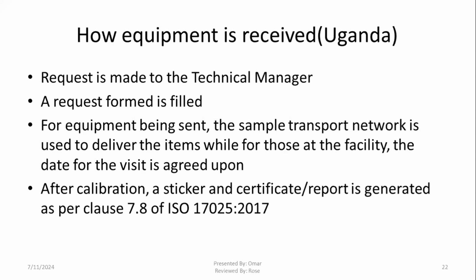So for those that are done at the client's facility, we work hand in hand with the IPs to ensure that this work is done. They do the logistics, and they enable the team to move from the calibration center to the client's facility. After the calibration is done, a sticker and a certificate are generated, as per clause 7.8 of ISO 17025:2017.